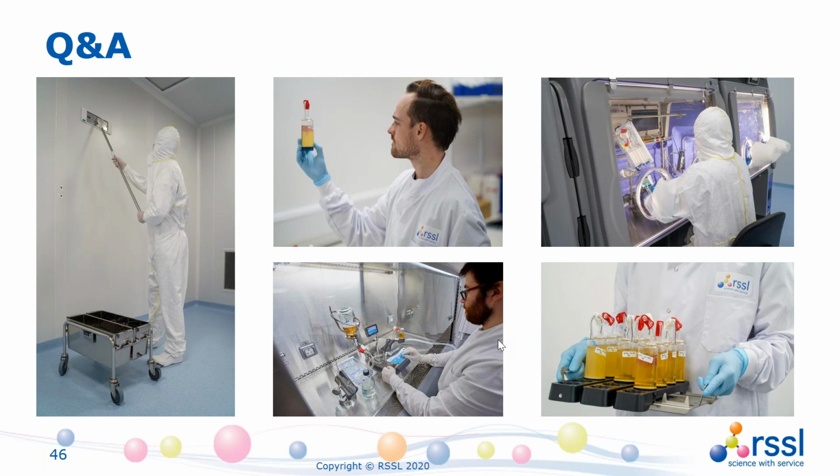Right, I see. Keeping to the environmental isolates for a moment, I've got a question from Thorsten about how many environmental isolates should be used in the validation. Again, obviously there's no guidance on that. It is a variable question. In my experience, it's between 2 and 4. It depends a little bit on what are the most common organisms you're finding from the facility, and also to develop the point I was saying earlier about how similar or dissimilar they are from what's included in the sterility test set.